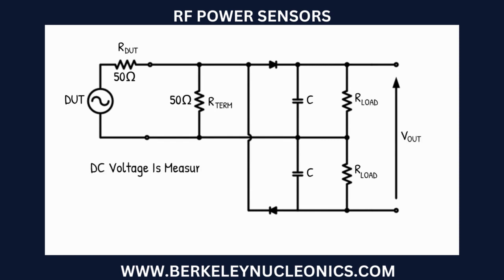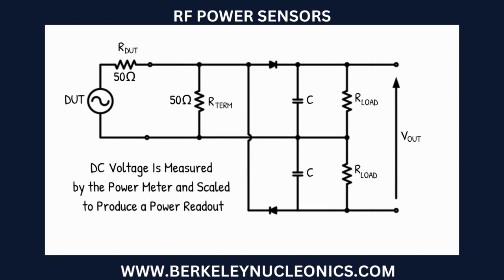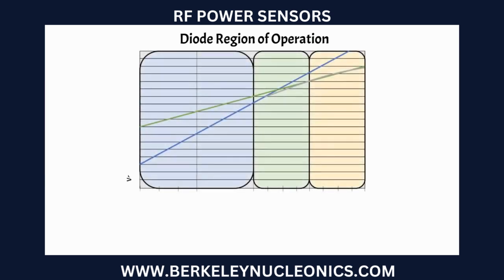How is RF power measured? High frequency diodes detect the RF voltage developed across a terminating load resistor. The diodes directly perform an AC to DC conversion, and the DC voltage is measured by the power meter and scaled to produce a power readout. The relation of the DC voltage to the power measured is dependent on the diode region of operation.